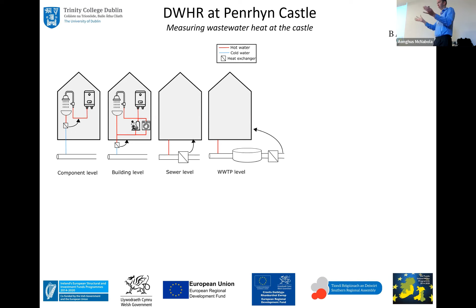So what we've done here in the castle is basically somewhere between these two. It's not capturing the whole building, which is what we tried to do in the beginning, and we'll see a map in a second showing where we started. We tried to capture the waste heat for the whole building, but too much of it was lost along the way, as our survey found. Instead we're capturing the waste heat not from a single process, but from a few in the kitchen.